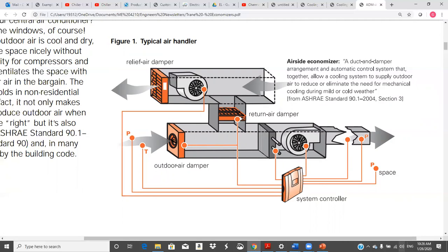But this is the fresh air, and it gets brought in the back of the air handler. It gets mixed, so we call this mixed air down in here, with this return air, and it goes back to the system. Now, if we want to use the open-the-window analogy, let's say we want 56 degrees, okay, what if it's 53 degrees outside? Well, does it make any sense to run a big chiller or a big piece of mechanical equipment to energize this coil to cool the air down? Wouldn't it be better if we could just take all of the air from outside at 53? By the time we blow it through this fan, it's going to pick up a degree or so, blow it out to the space. Oh man, perfect. And all I'm doing is basically running a fan, okay?